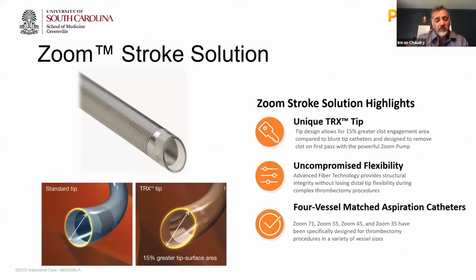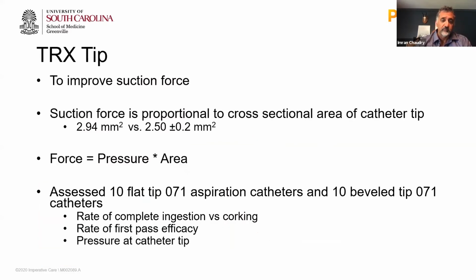The intention of the bevel tip was to improve the surface tip area and basically to improve the clot engagement area of the catheter. And I'll show you a couple of videos as to why this is beneficial. In addition, the bevel tip actually improves navigation. At first, when I saw this, I thought that the tip would actually impede navigation, catching on vessels, but it tends to reorient itself in a configuration that allows you to navigate into the target vessel very easily. These catheters are all designed with a distal flexibility to navigate very easily in an atraumatic fashion to the target vessel. In addition to improving the surface area and the contact area for the clot, the bevel tip actually improves suction force. Suction force is proportional to the cross-sectional area of a catheter tip, and we can see when compared to a flat tip catheter, there's a significant increase in the force that's available for aspiration at the catheter tip.